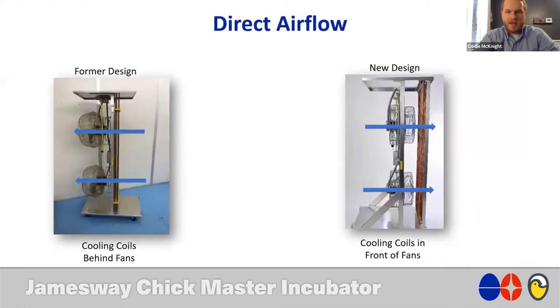Here you can see our former design next to the new design. With the former design, you have that air inlet coming directly onto the fan coil and then being pulled by the fan through the coil and pushed into the cabinet. With the new design, we have turned that around. That air inlet is closer to the fan. The fan is going to pull that air directly out of the inlet and push it through the cooling coil to condition it more efficiently. You don't have the chick down. You're moving more air with a more efficient fan. It's going to improve your performance. And like I said, even if you're performing at the highest level, doing so more efficiently is always a good thing.